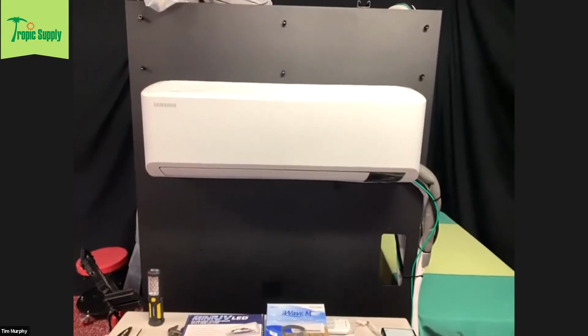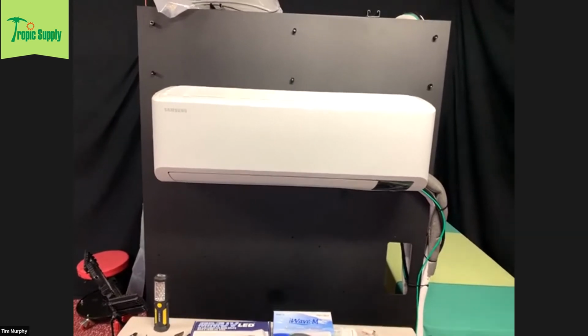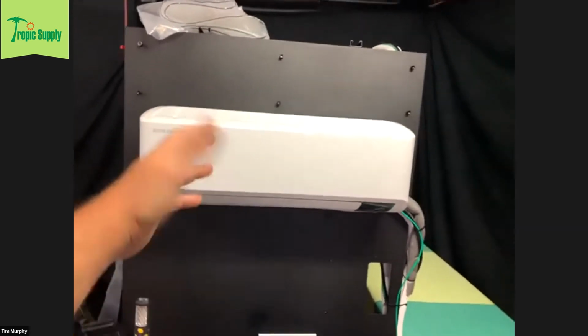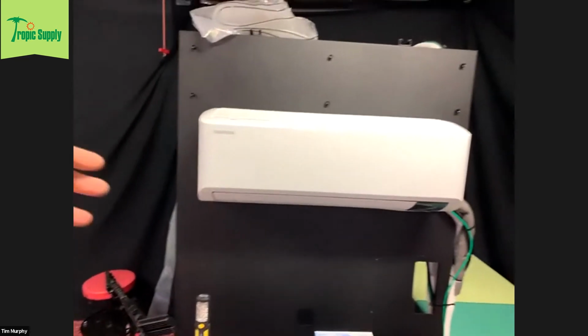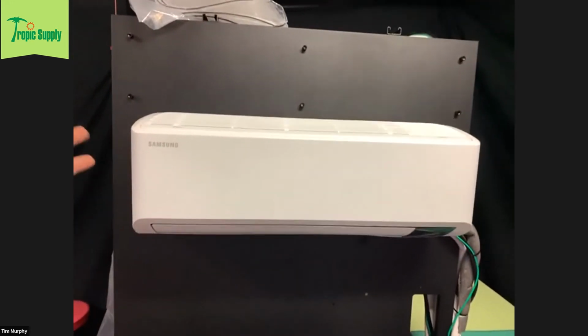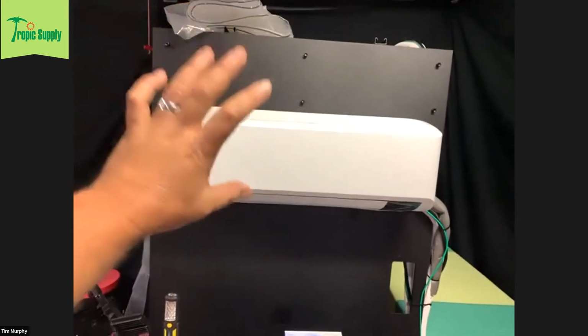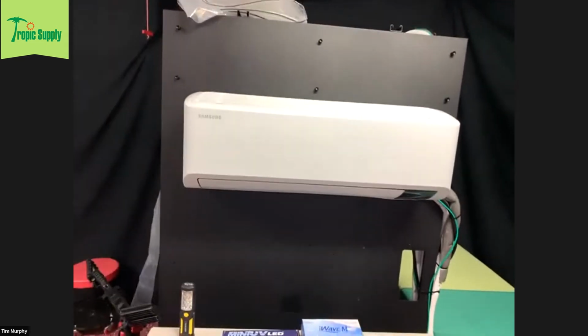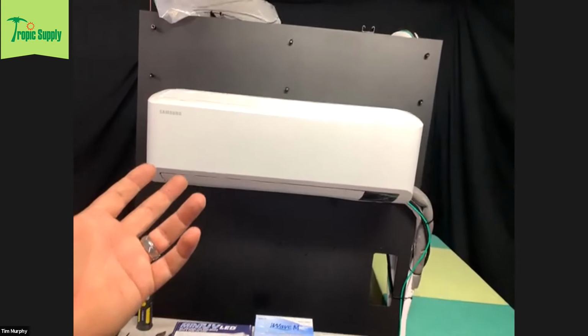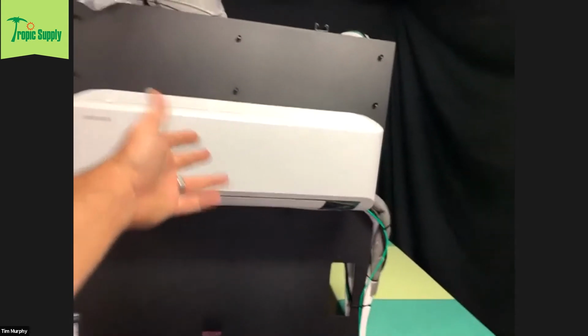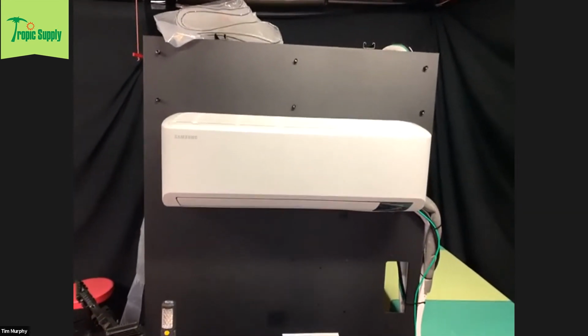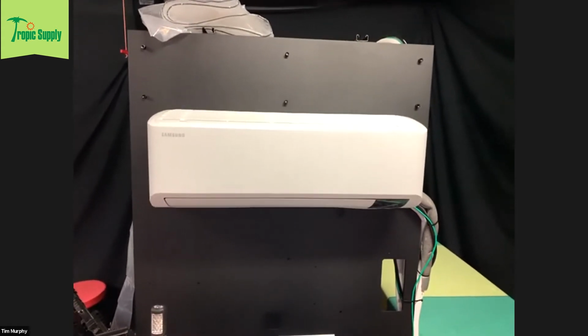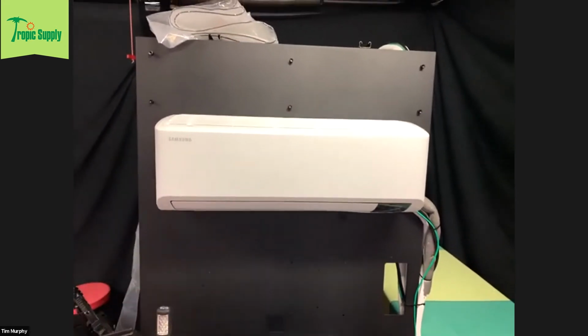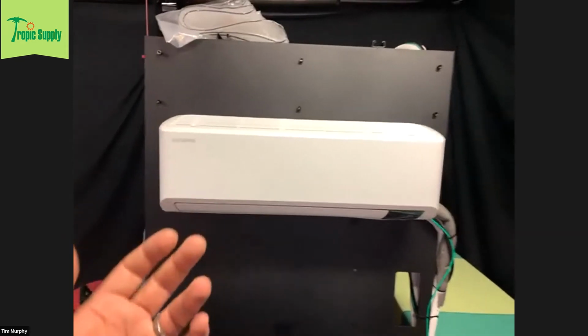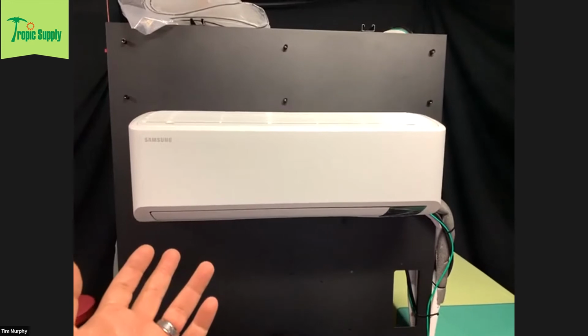A follow-up question: why do we pump down? Say you have a high wall system and the customer wants to paint the wall, or there's a leak or some damage to the system, but it's not going to be a full change out. Just like any other system, you're going to want to pump the Freon down and keep it, you don't want to lose it. That would apply if a customer wants to move the high wall unit to another area. Anytime you're breaking the line set, cutting the copper, extending the copper, relocating the system, or removing it from the installed location, that's when you need to pump it down. Other than that, doing the maintenance like what I'm doing today, you will not need to pump down the system. Hopefully that answers the question.